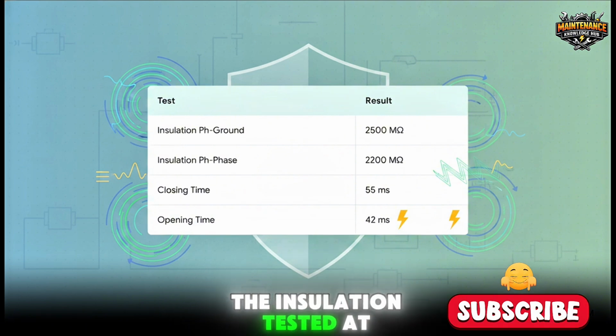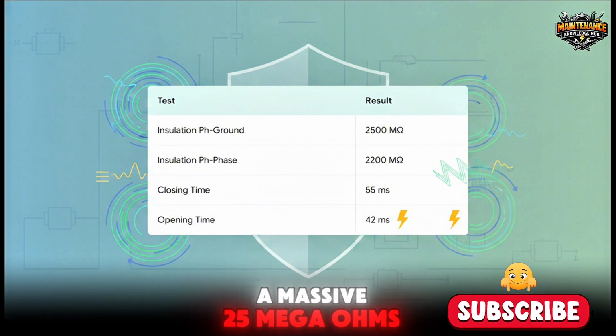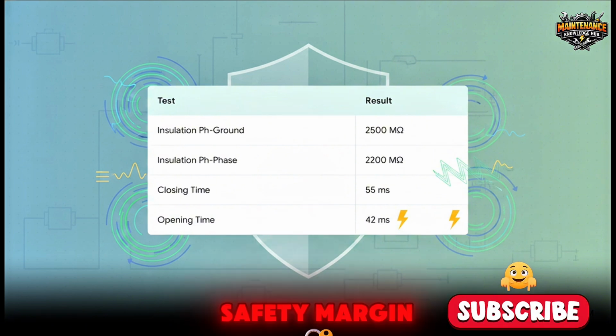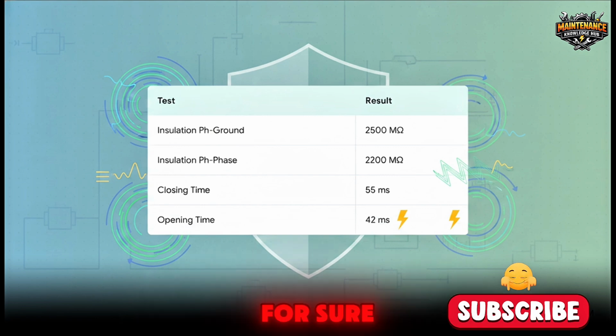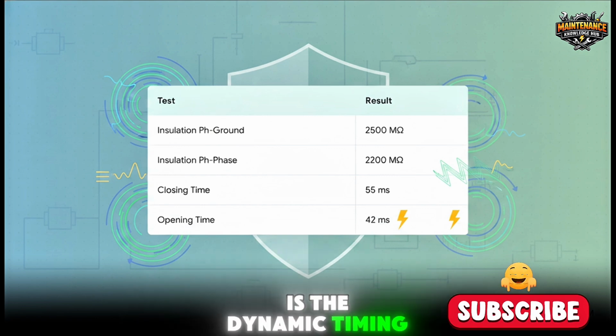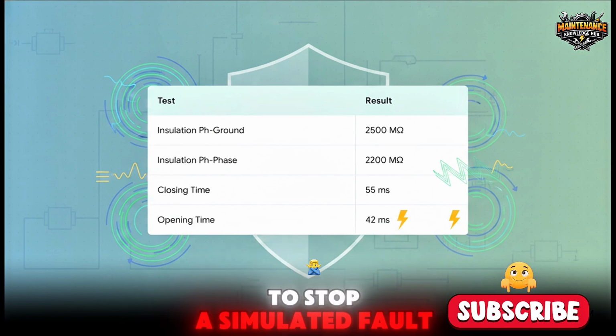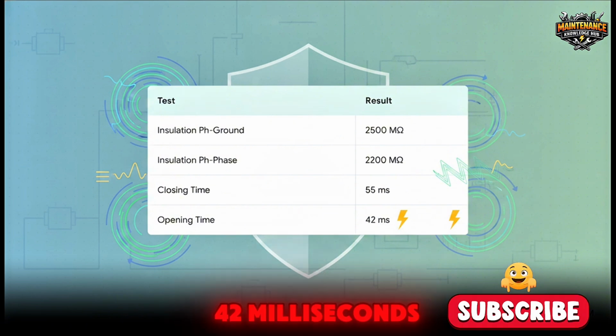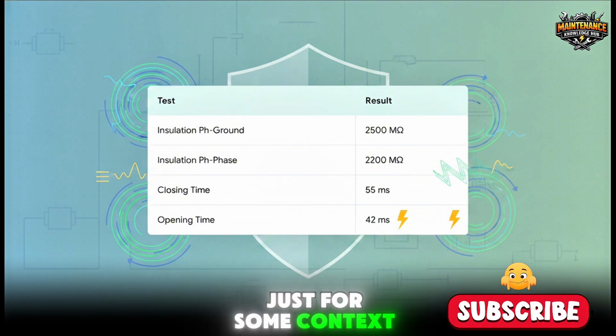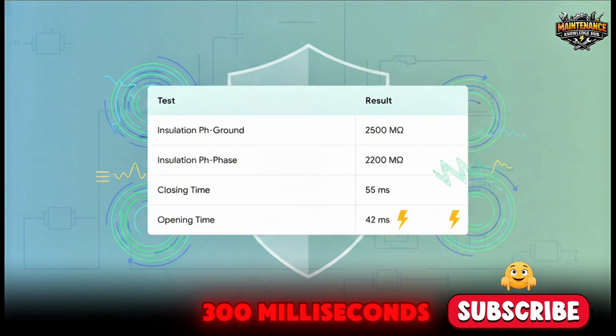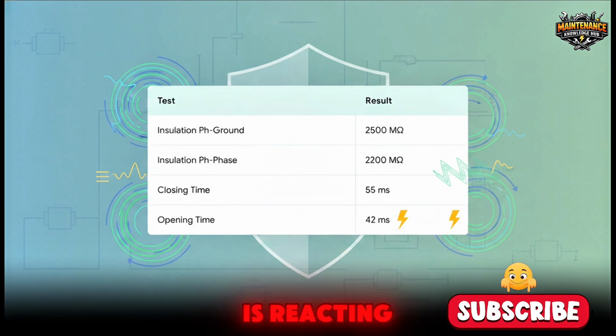Now, the results here are honestly pretty mind-blowing when you think about the sheer scale and speed. The insulation tested at a massive 2,500 megaohms, which gives us plenty of safety margin. But the most impressive part, for sure, is the dynamic timing. This breaker snapped open to stop a simulated fault in a lightning-fast 42 milliseconds. Just for some context, a human blink takes about 300 milliseconds. So this piece of equipment is reacting nearly 10 times faster than the blink of an eye just to keep the grid safe.